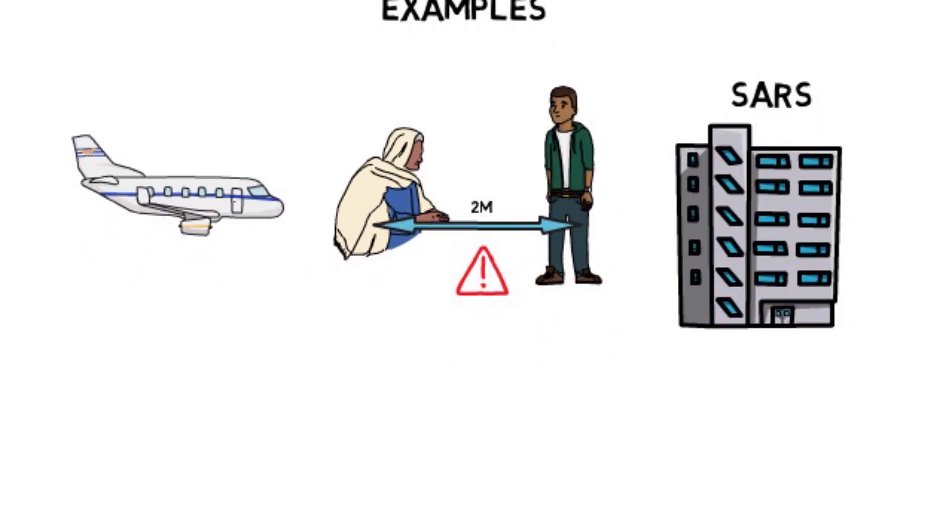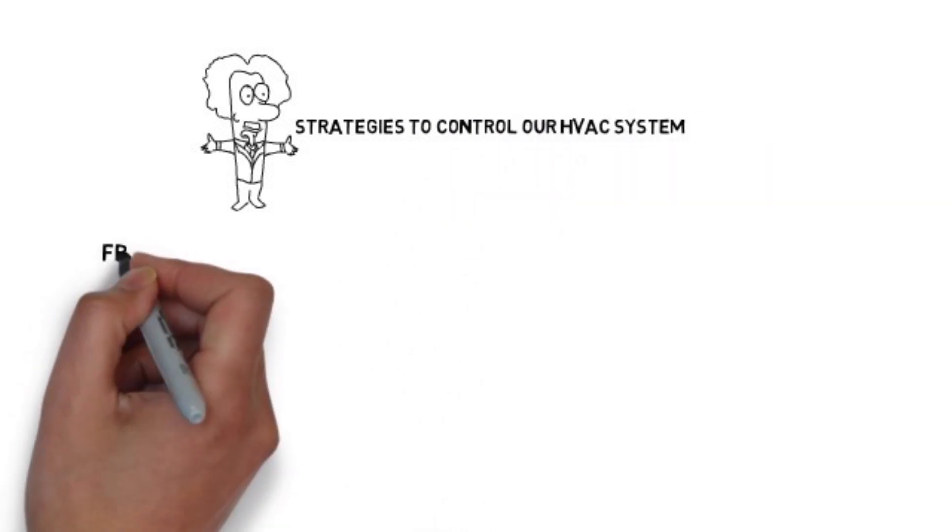Since we don't know yet if the new COVID-19 coronavirus can transmit through aerosols, what are the strategies to control our HVAC systems to minimize the risk of infection in buildings? First, increase the outdoor airflow rate, bringing more fresh air into the room to dilute the droplet concentration, possibly by natural ventilation, opening windows more often.